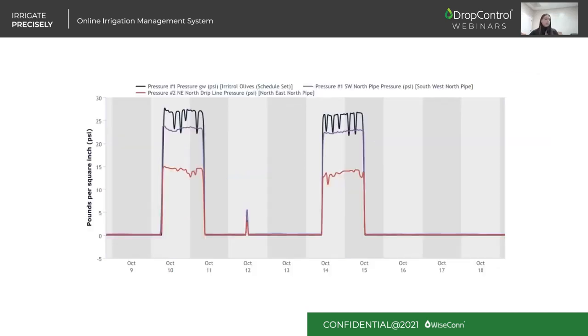Pressure throughout a system: on custom charts you're also able to read pressures for 3 to 4 different pumps. Right now we're seeing 3 different pumps over a 2-week span. If we were on DropControl, we'd be able to hover our cursor over these tracks—the black, purple, and red—and see the exact PSI for every minute of every day over those 2 weeks.